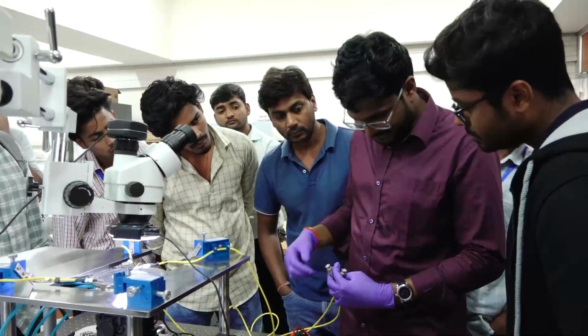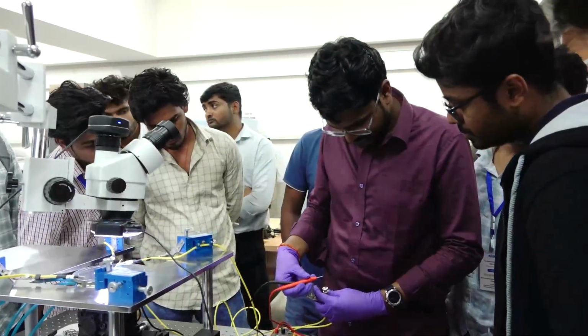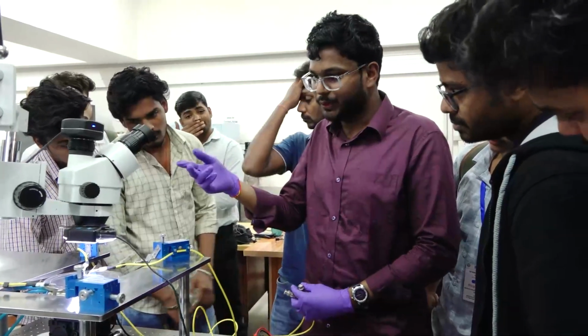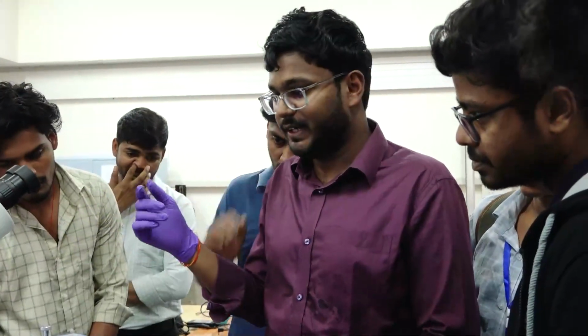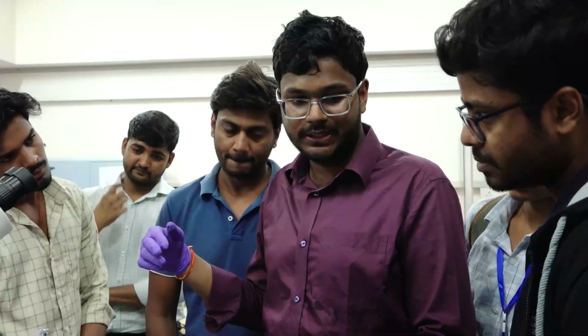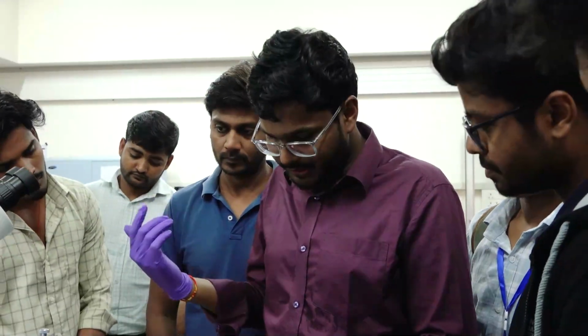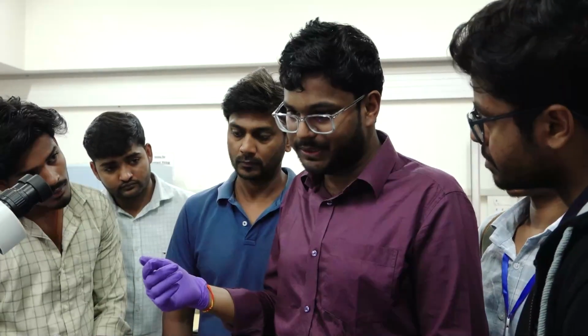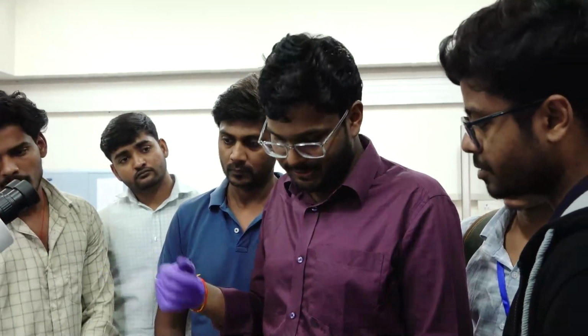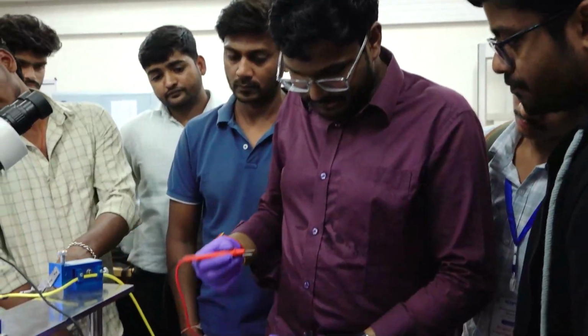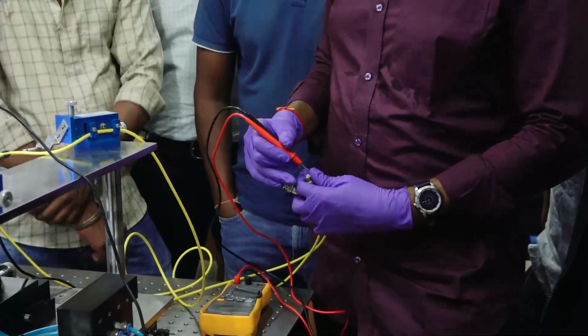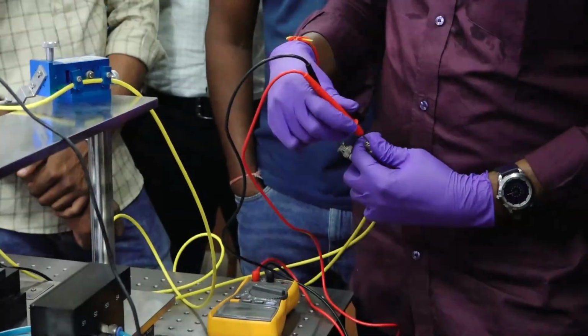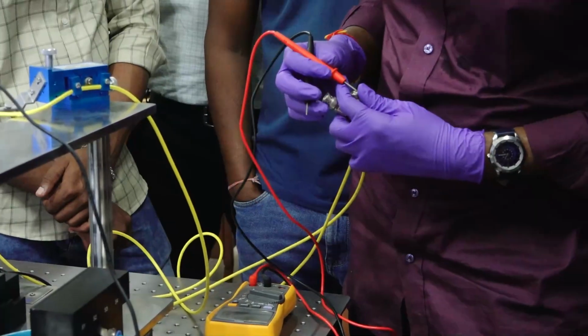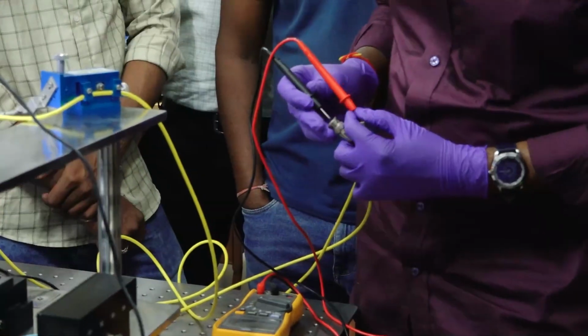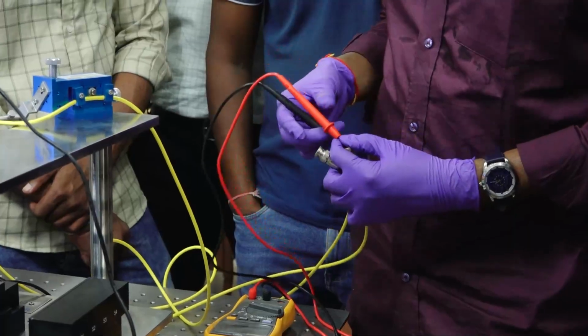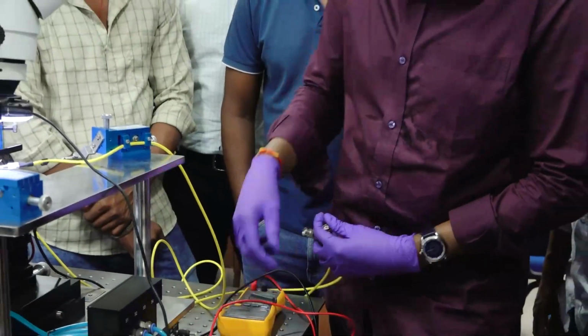These are triax connectors, right? Inside there is a metal connection. Since we have connected our probes to the same metal, if we connect the probe tips to the same metal, it is like a closed connection. So how will we ensure whether our probe tips touched our metal pad perfectly or not? You can go with this multimeter short check. Go for this metal tip. You can touch this. When the sound comes, then it's a short. Then once it is short, then you can see.